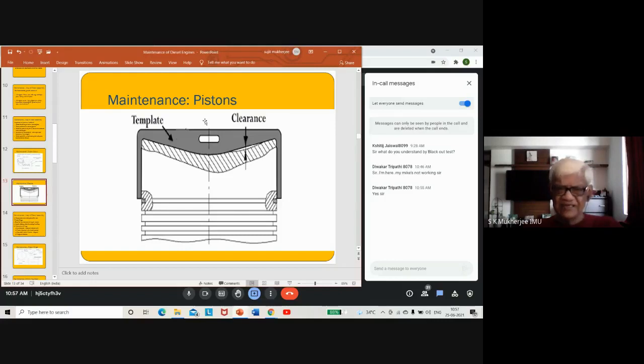What is the hazard here? The wall thickness of the piston crown has become thinner and it may fail in time to come. So this record has to be made and sent to the company. The company may say that at the next overhaul period, change the piston crown and send the piston crown for reconditioning.